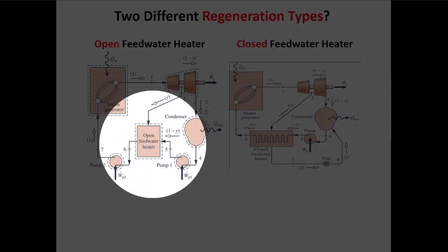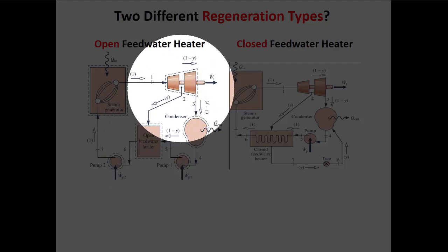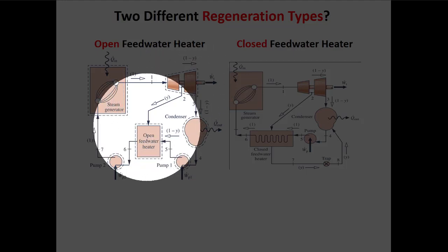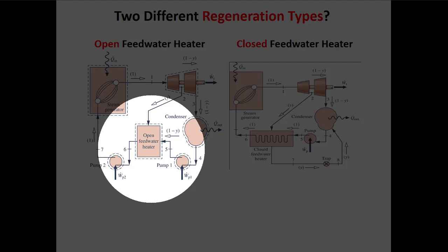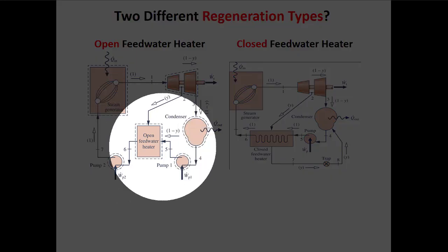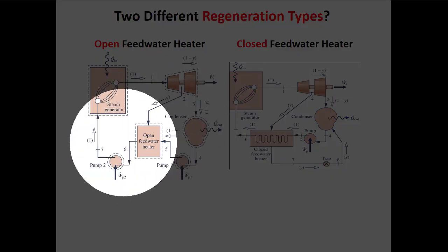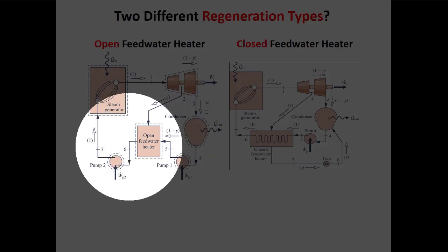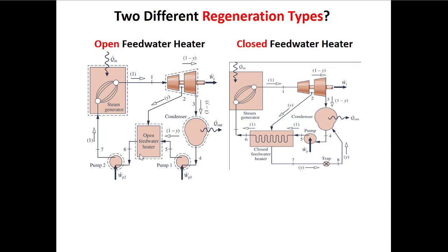Generally, there are two different types of regeneration systems, defined by what happens in the feed water heater. The feed water heater is the heat exchanger used to transfer heat from the hot flow bled off after the first turbine to the cold flow that's been condensed. In the open feed water heater, two streams of mass meet together under the same pressure in a reservoir — like a sink with a hot tap and a cold tap mixing in a basin. You have two inlets and one outlet: the hot side, the cold side, and a warm fluid coming out at state six.